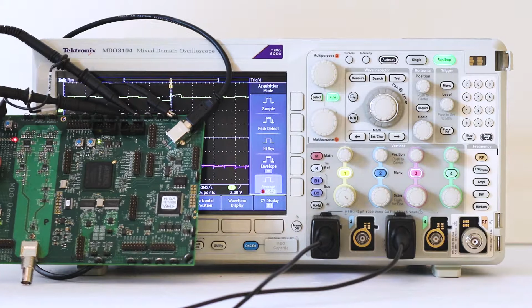If the signals that appear in the oscilloscope display are quite blurry, they can be cleaned up by performing a signal averaging operation. This is done quite simply by pressing acquire, then mode, and average. By averaging multiple waveforms, the successive images are superimposed and reinforce one another, while noise, which is random, cancels out. This works only, of course, when the waveforms are repetitive. The number of waveforms to be averaged ranges from 2 to 512, set by multipurpose knob A.